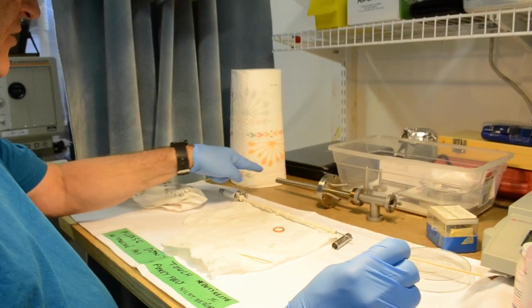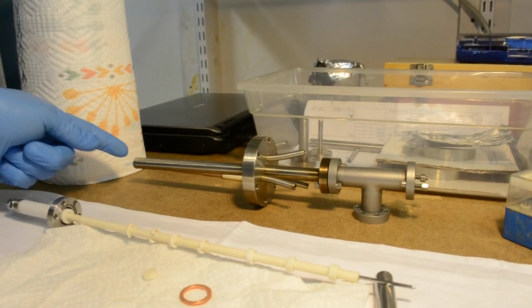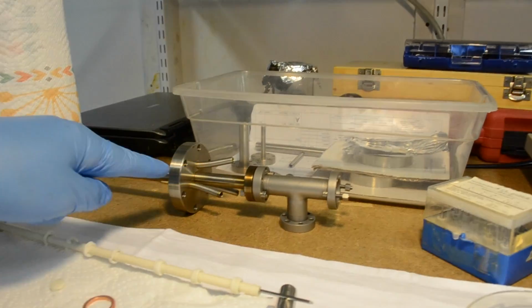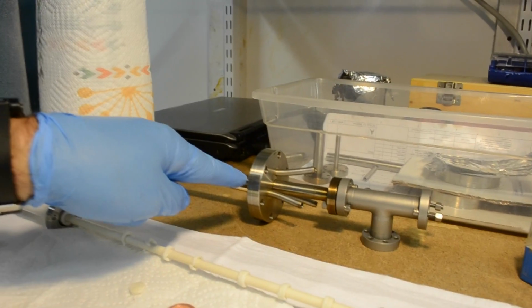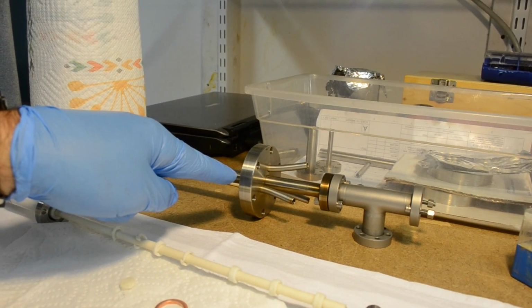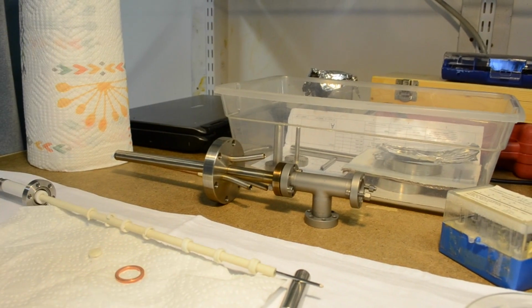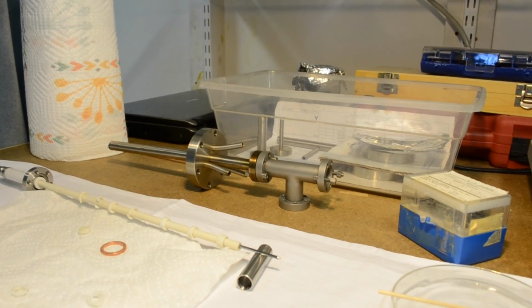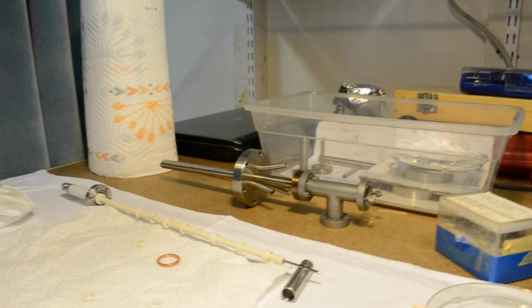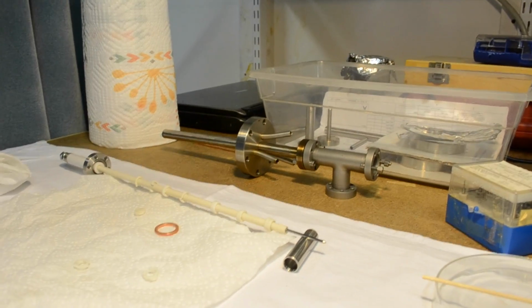So this is the cell itself. This is the bottom, and then this is nothing but a 1/2-inch tube up to this point. This flange is welded on the outside and will connect to the outer vacuum chamber. These tubes here are pass-throughs for electrical stuff like RTDs, thermocouples, heater wires, and possibly an electromagnetic coil.